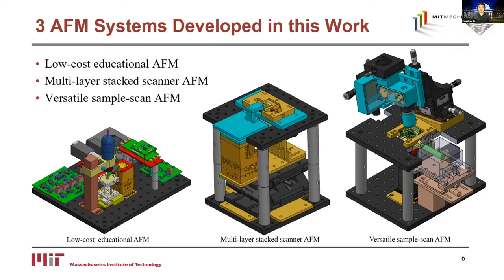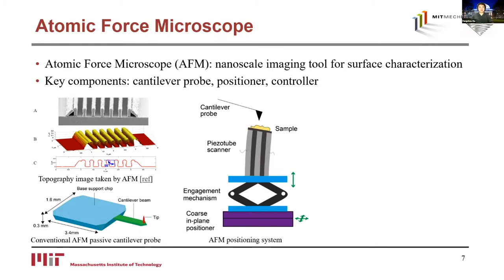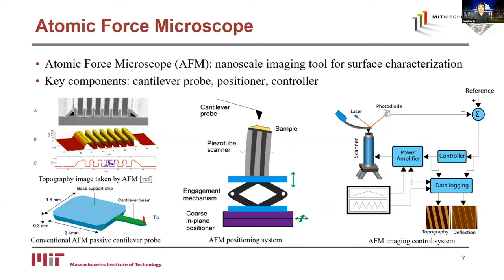We'll begin with a brief overview of atomic force microscopes for audiences not very familiar with this instrument. AFM is a nanoscale topography imaging tool for surface characterization. In its basic form, it creates a 3D topography image of a sample surface with sub-nanometer resolution. The key components of an AFM include a cantilever probe, a nano-positioning system with a coarse engagement part and a high-resolution scanner, and an imaging control system. An AFM scans the micro-cantilever over the sample surface to measure various quantities from the probe-sample interaction.